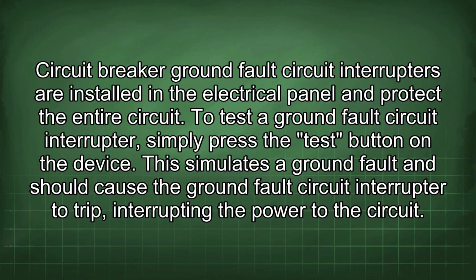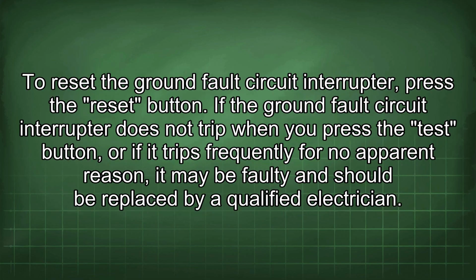To test a ground fault circuit interrupter, simply press the test button on the device. This simulates a ground fault and should cause the ground fault circuit interrupter to trip, interrupting the power to the circuit. To reset the ground fault circuit interrupter, press the reset button. If the ground fault circuit interrupter does not trip when you press the test button, or if it trips frequently for no apparent reason, it may be faulty and should be replaced by a qualified electrician.